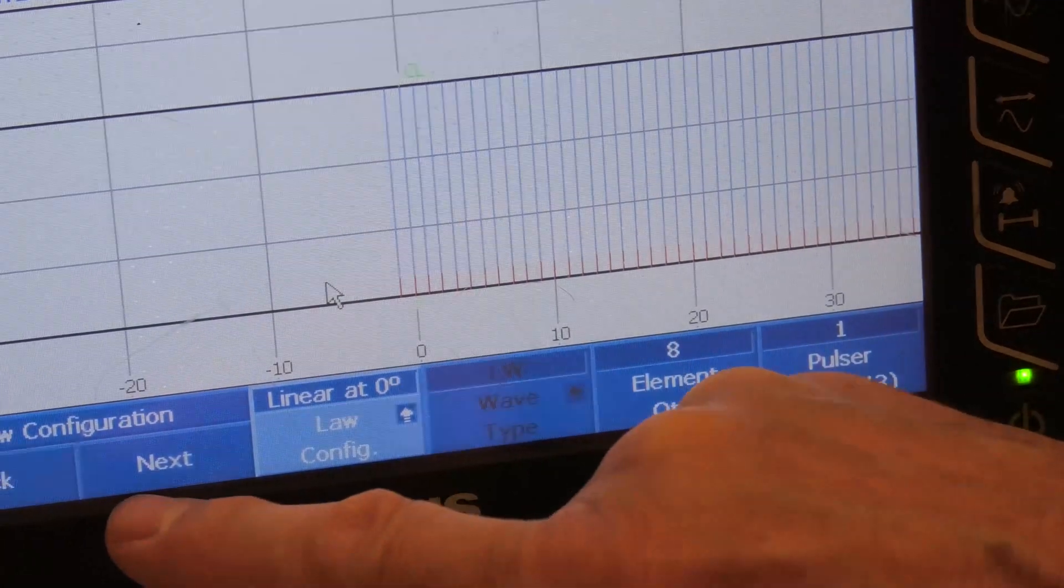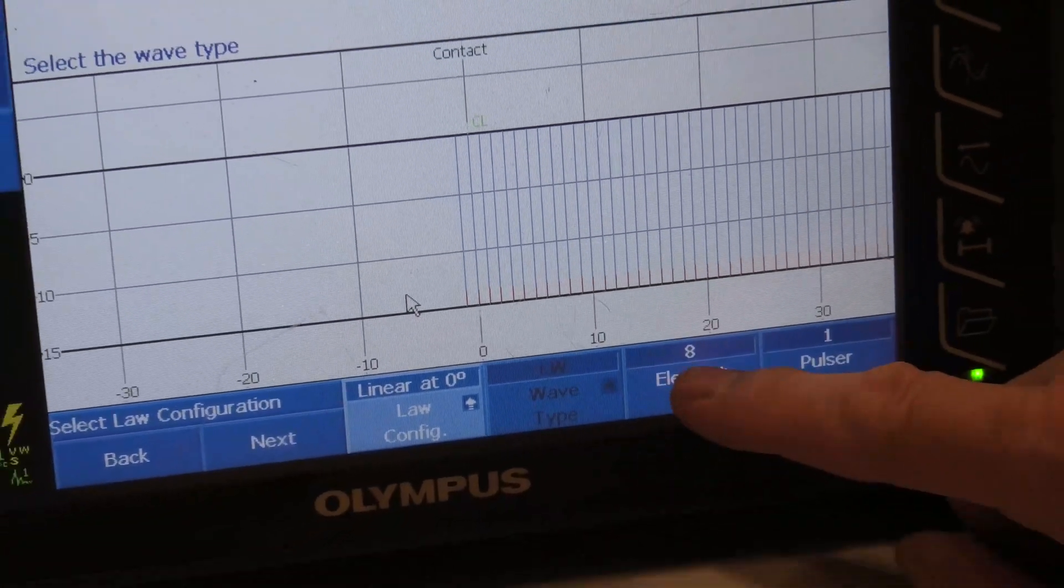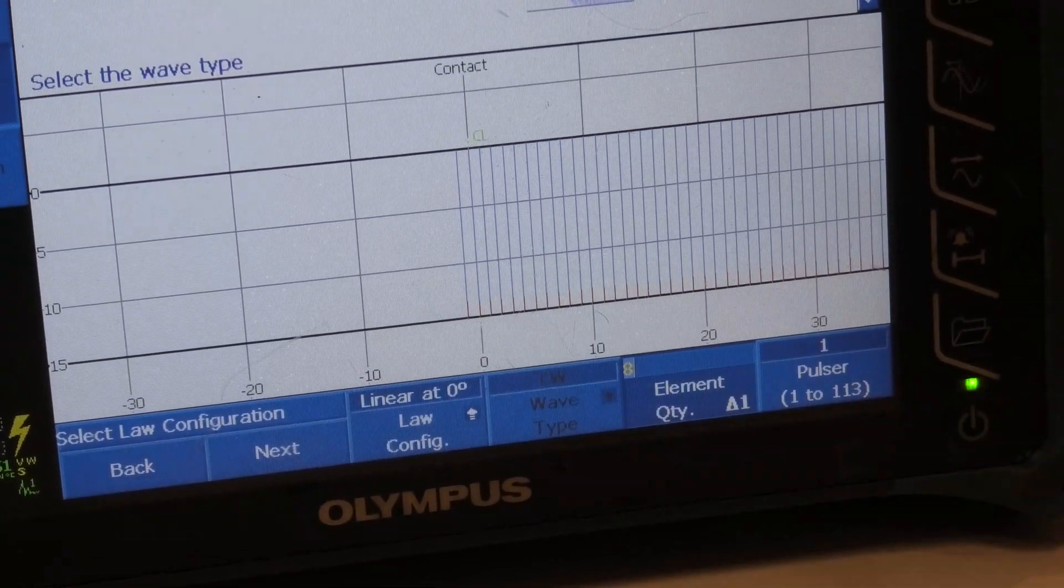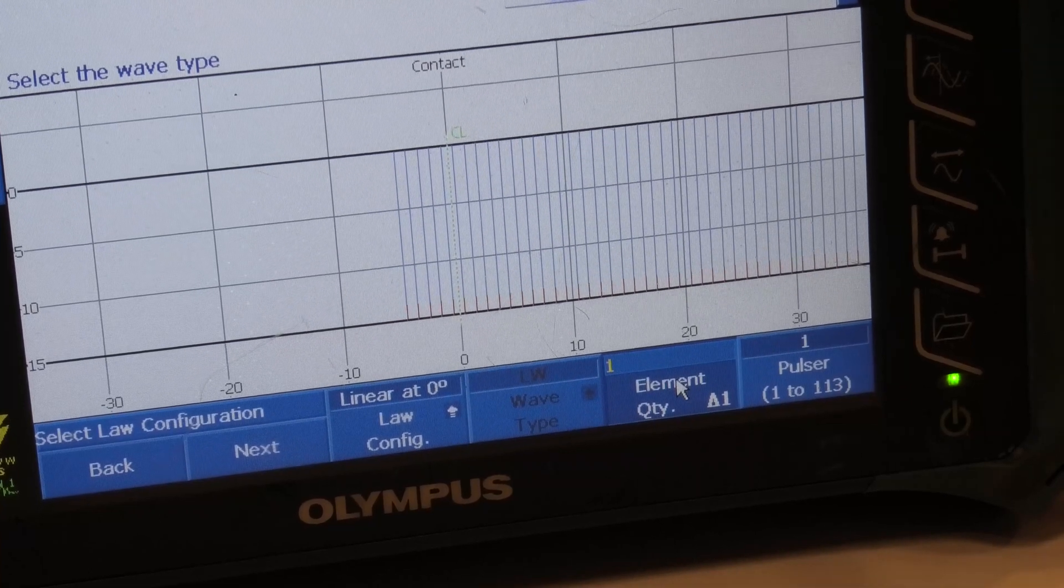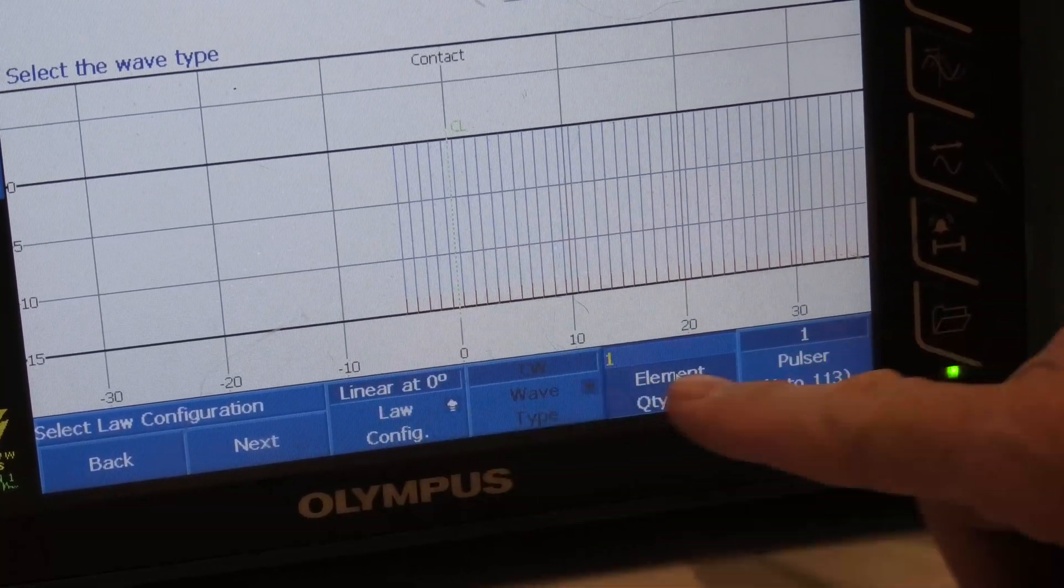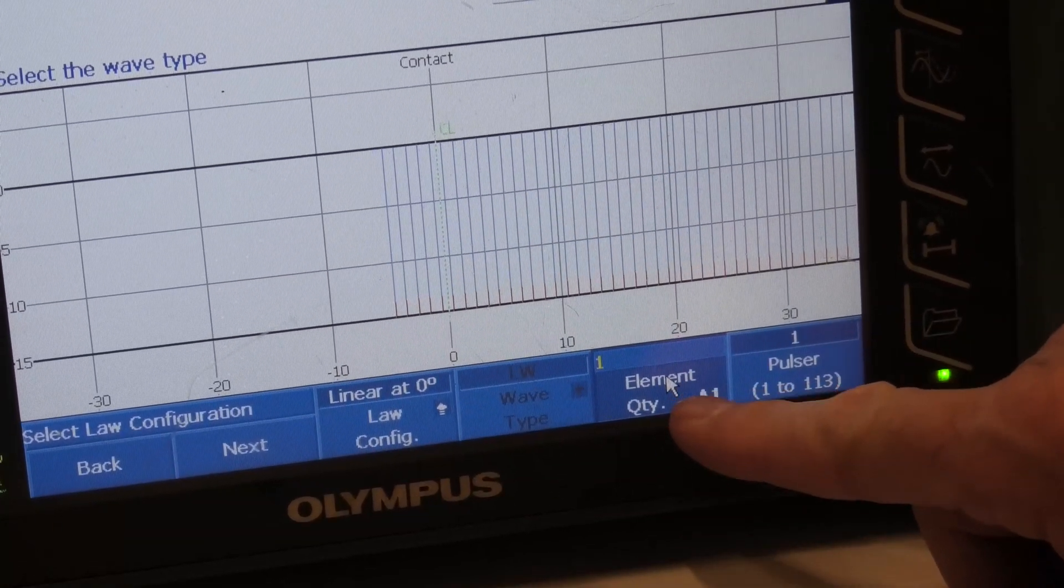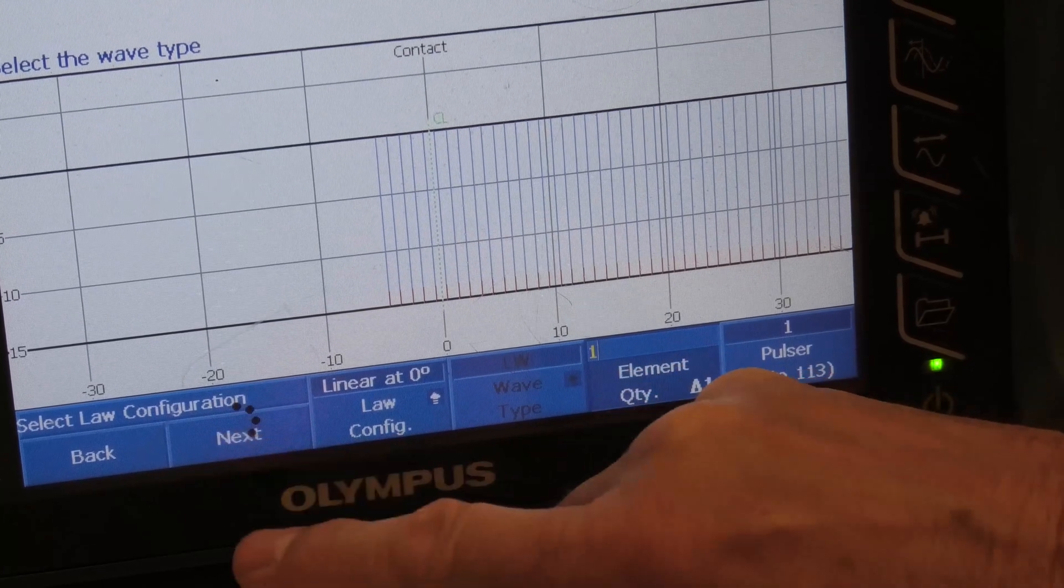Okay, we now hit—sorry, element quantity, I'll need to set that back down to one. So it's linear at zero degrees, the element quantity has to be one. Next.